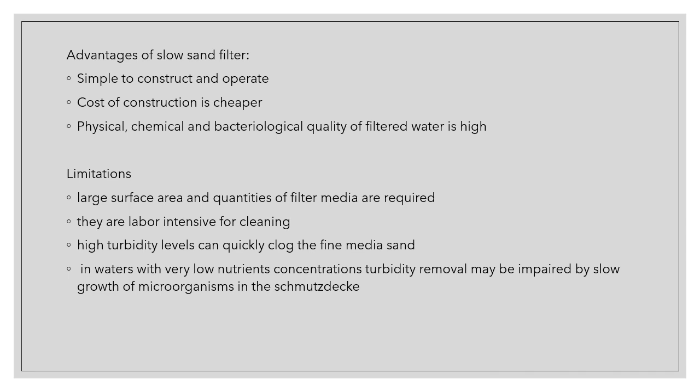However, there are certain limitations. A large surface area and quantity of filter media is required. They are labor intensive for cleaning. A high turbidity level can clog the fine media sand. And in waters with very low nutrient concentrations, the turbidity removal actually may be impaired by the slow growth of microorganisms in the schmutzdecke.